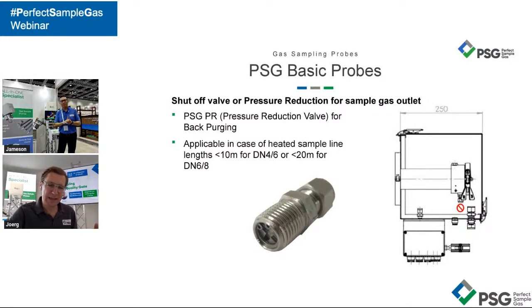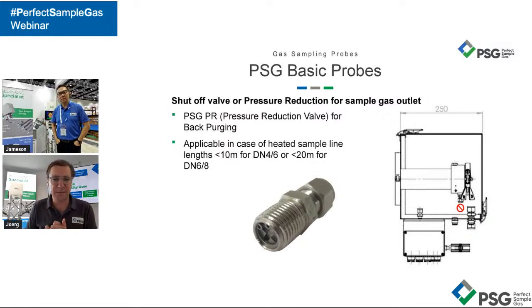So this is more or less a protection for the connected heated sample line. We always have to consider the entire system. We saw that when we had a look at the P&ID. The entire system is heated up to 180 degrees C, for example, and we use Teflon tubing for the probe transportation, which again means a high pressure can be a stress for this system. So this is a good way to protect the sample handling system, which comes after the gas sampling probe, and obviously at the end also the analyzer.